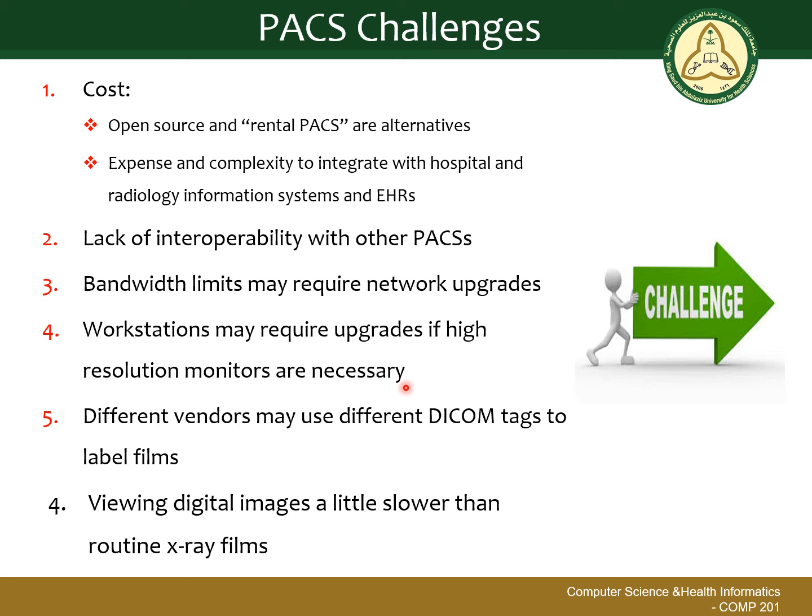So if there is a need for higher resolution, we need to upgrade the workstations, and different vendors may use different DICOM tags to label the films. So there is not one tag that can be used, because each vendor will use different DICOM tags to label the films.